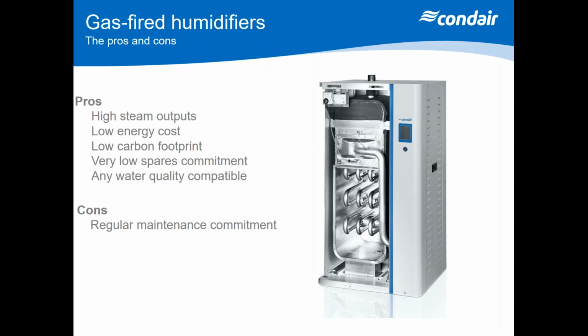So they're big units. Now, these tend to be supplied in either what we call a gauze face burner, as you can see here, which gives you very, very high efficiency to transfer the heat from these heat exchangers into your water to get it to boil. Or you can also see a 360-degree radial burner, which will give you controllability as well. Now, with these systems, very similar to the resistive, you can use them with different types of water. You can use your RO water, your softened water if you want to.